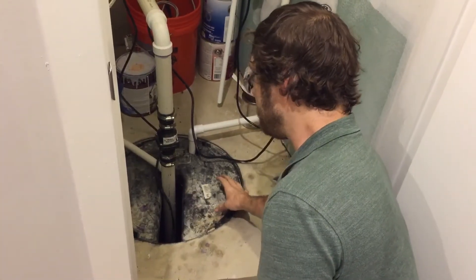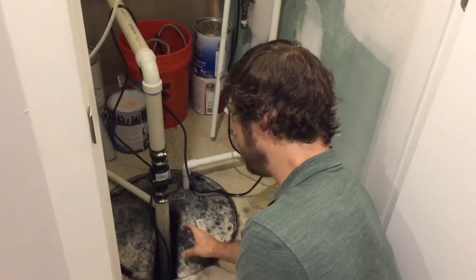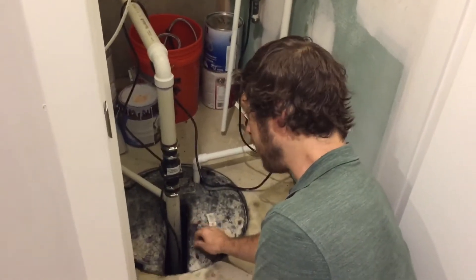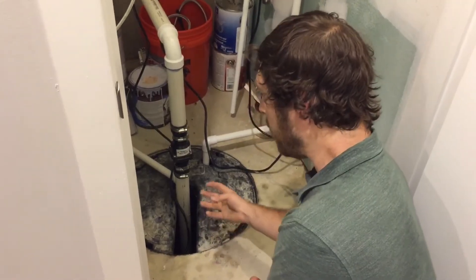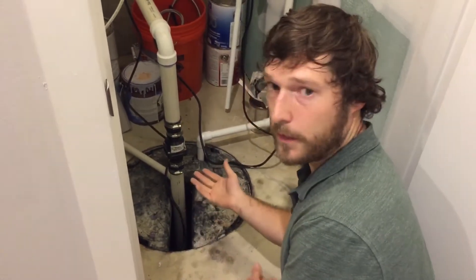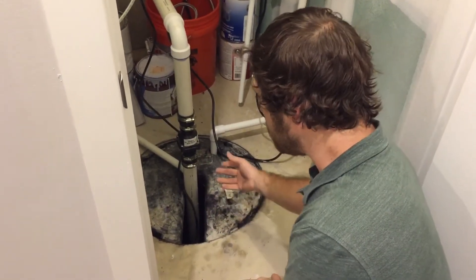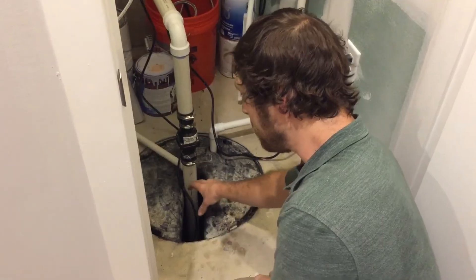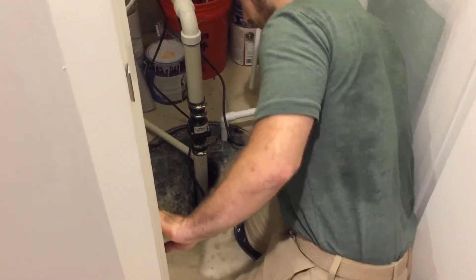So what you have to do to maintain this is actually not really that much. I talked to Zoeller, the manufacturer of our pump, and they said that there's really not much maintenance required at all. All you have to do is exercise it every now and then — make it run — otherwise the seals will dry up and get brittle. So what you can do is either pour a big bucket of water in here, or you can get in there yourself. I'm going to show you how to do that.